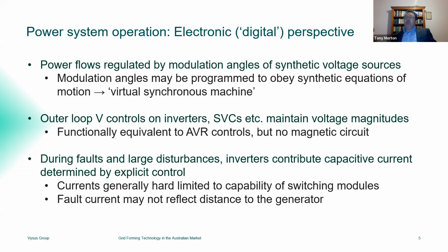And then when we have faults in the network, we have a rather different picture of how the inverter contributes to the fault. It's no longer purely a passive contribution determined by Ohm's law, because quite often these inverters will go into a current limiting mode. And the fault contribution for these inverters often has to be explicitly controlled. So on the one hand, we have the flexibility to say the inverter should make a contribution according to the depth of the voltage dip, according to some rule which can then get programmed into the firmware. But on the other hand, we don't have that automatic proxy for electrical distance that determines what your fault current is going to be and allows you to coordinate your protection.